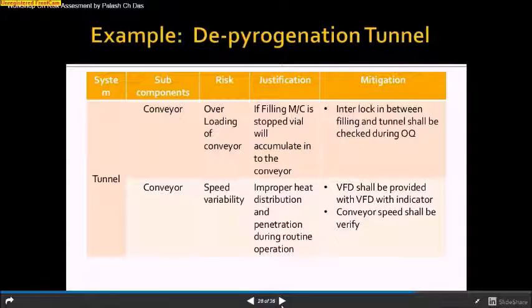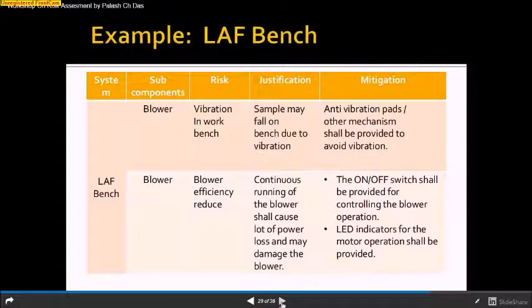Second one, the blower. The blower efficiency is reduced. There is a possibility of running the blower for 24 hours, so the blower efficiency will be reduced, and we should stop the blower. Continuous running of the blower can cause a lot of power loss and maybe damage to the blower. So there should be an on/off switch to control the blower operation, and you should have a timer also. It's a new point I am discussing.